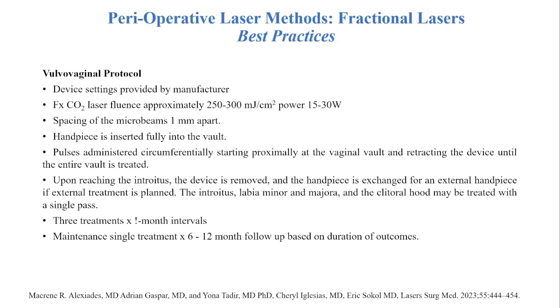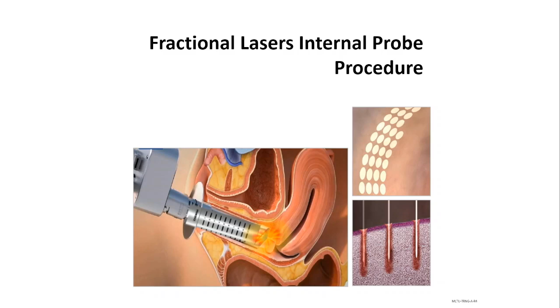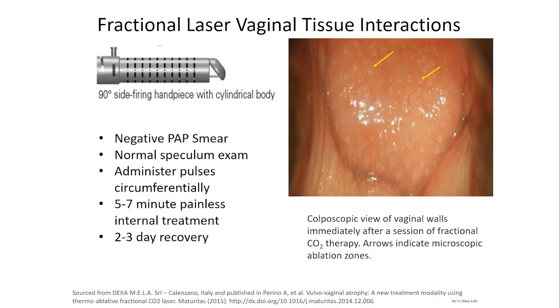And this is just to show the pictorial of an example of a fractional handpiece being inserted into the vault, and you can see the markings on it that are centimeter markings. Some of them have an automatic discharge in a 360-degree circumference. Others, you have to turn the handpiece manually and then retract, turn the handpiece manually, fire, and retract. And this is just what it looks like right after treatment. What you see colposcopically are microscopic ablation zones, which are tiny white circular macules. And the recovery following this is 2 to 3 days in terms of reepithelialization.